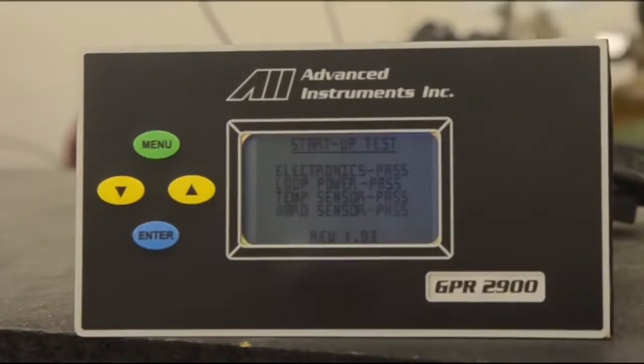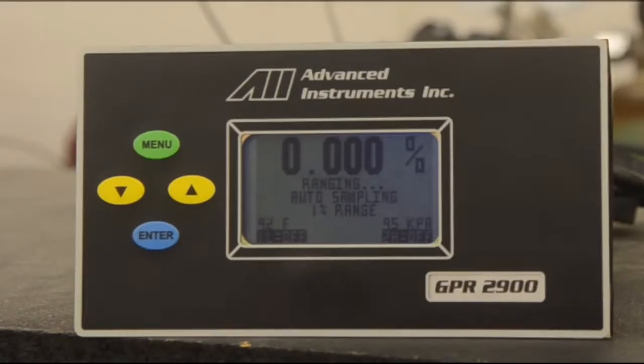Now, as you can see on the menu, the system does a startup test when power is first received to the unit. Confirm that all tests are passed. Once that happens, you're going to be taken to the main screen of the analyzer. Right now, we're reading 0%, which is what you should be reading when you first power this unit on.